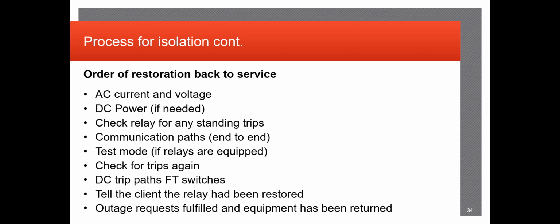So doing your communication paths, checking for trips again. You want to identify that there are no standing trips all the way up until you actually put in the DC trip paths. And if you make it all the way through, put all your stuff back in, tell the client the relay has been restored, the outage request has been fulfilled, and the equipment is in service permanently. Once that's all squared away, usually the client will request a physical measurement as well as a screenshot of the relay reading currents and voltages, phase angles, verifying that there are no standing trips and that when you put it into service, it was working properly. That way, if something were to happen after you leave the site, it worked when we left, so something must have happened, whether it be a fault or whatever. So again, going back to covering your ass, making sure that you verify everything works properly.